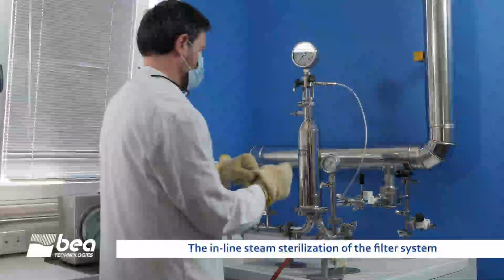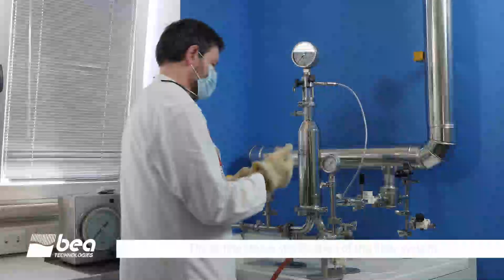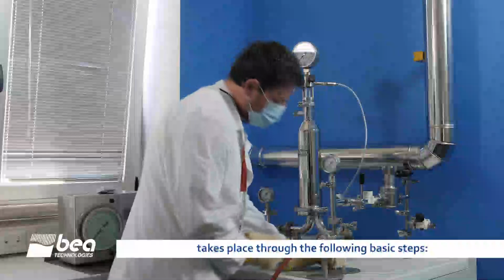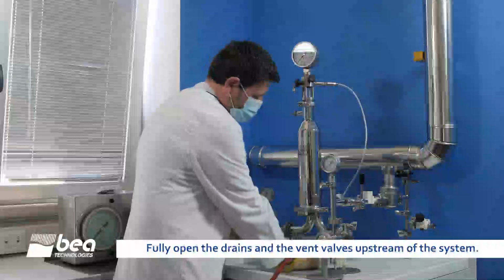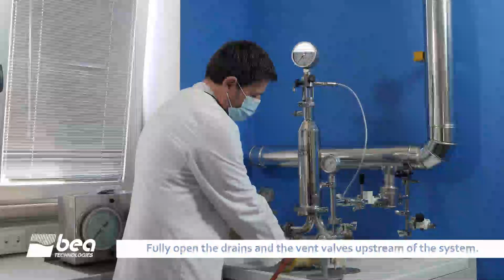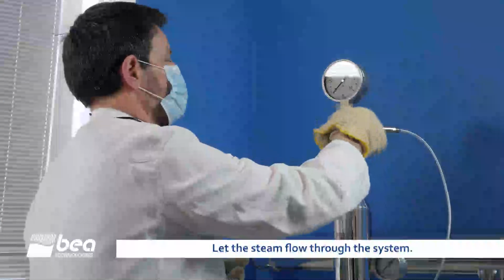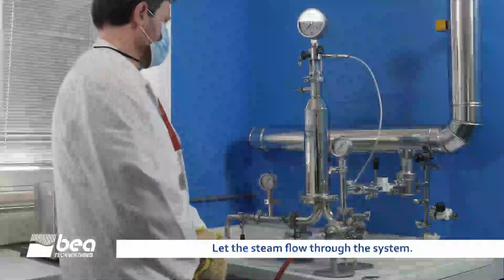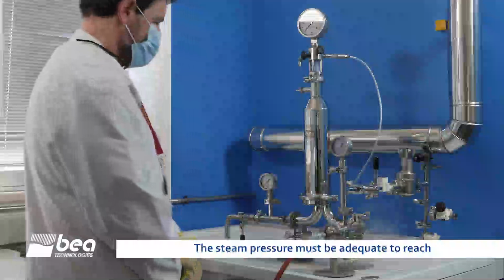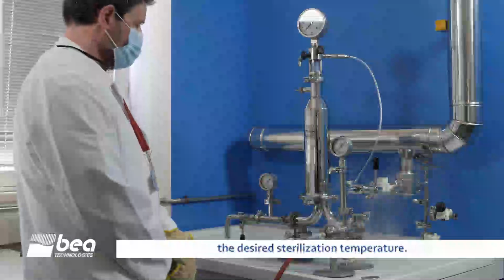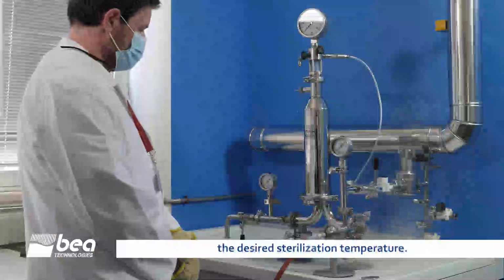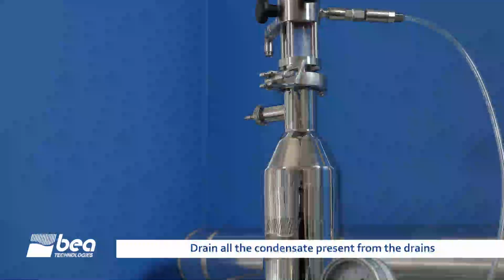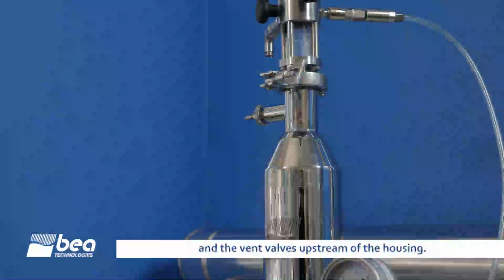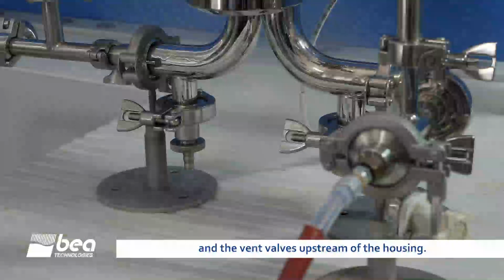The inline steam sterilization of the filter system takes place through the following basic steps. Fully open the drains and vent valves upstream of the system. Let the steam flow through the system. The steam pressure must be adequate to reach the desired sterilization temperature. Drain all the condensate present from the drains and the vent valve upstream of the housing.